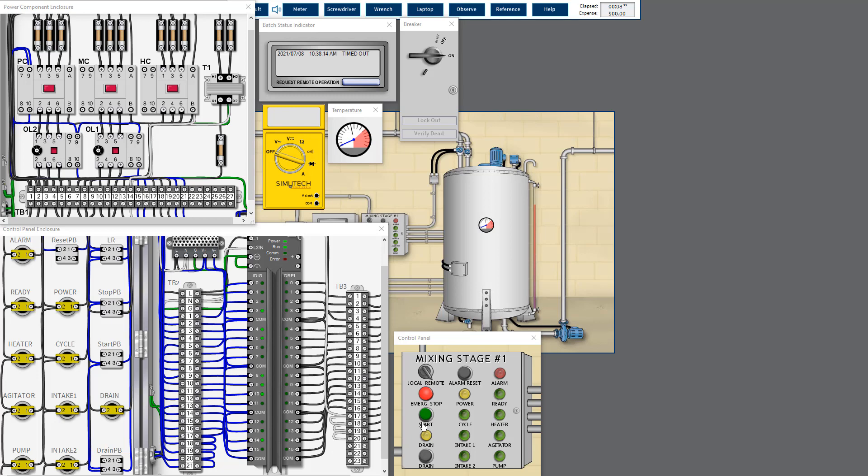At first, by looking at the external device and circuit, I noticed that there is no lighting from the control panel and I noticed the EMO switch or button was pressed by someone. So I release it and there's lighting from the power lighting.